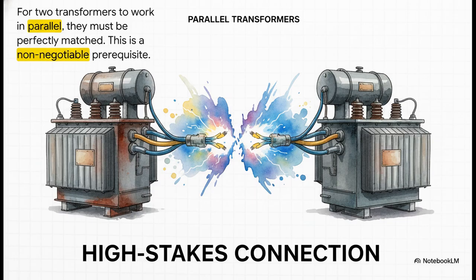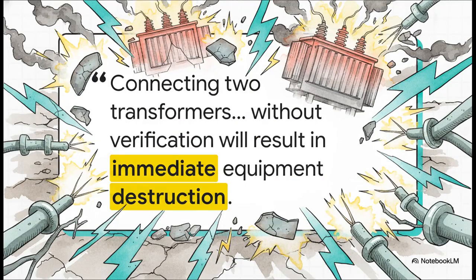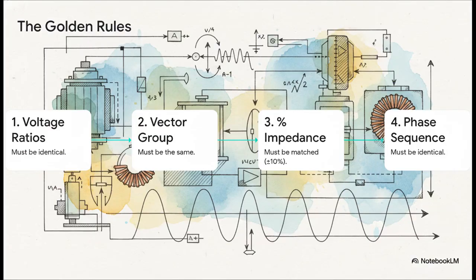It's a high-stakes team effort. And I mean high stakes. Get this wrong, and you're looking at catastrophic, explosive failure. No joke. To avoid that, there are 4 golden rules: everything has to match — voltage, vector group, impedance, and phase.